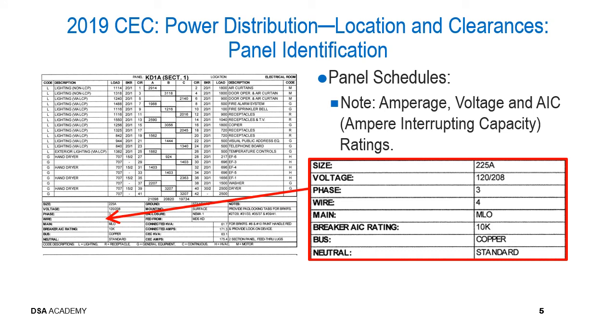Let's talk now about panel identification. On the left of this slide, you'll see an excerpt from a plan set that actually shows a panel schedule. And this particular panel schedule identifies the details for panel KD1A, Section 1. And we have a blow-up of a small portion of this panel identification schedule on the right hand side, and you can see that it shows some very simple parameters for the panel itself, such as the size is 225 amps, the voltage for the panel is 120/208 volts, it's 3-phase, 4-wire, the main is an MLO main, and the breaker AIC rating, which is ampere interrupting capacity rating, is 10,000 amps.